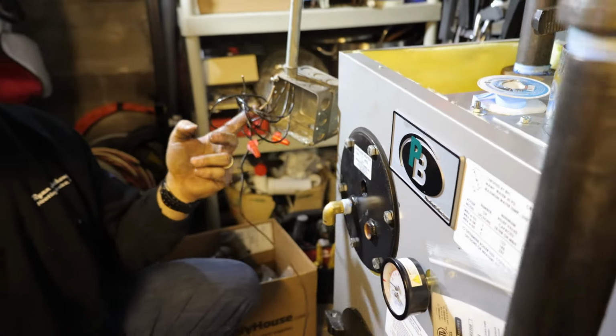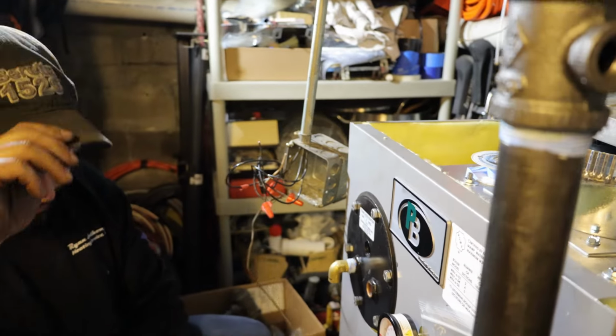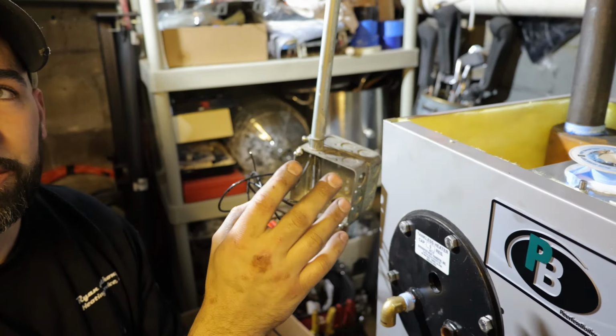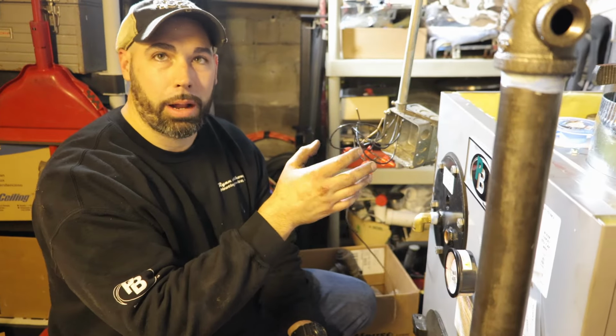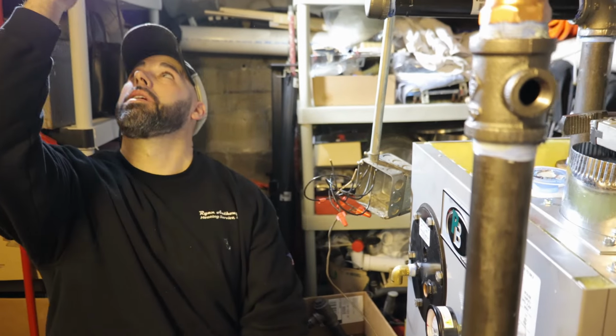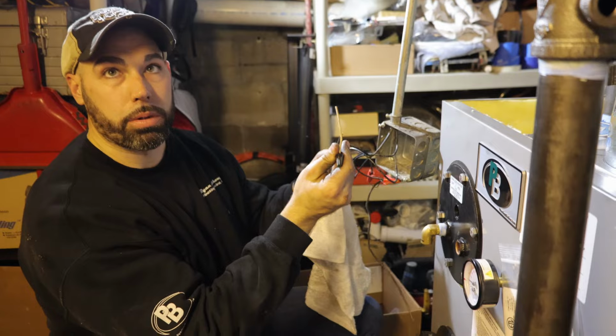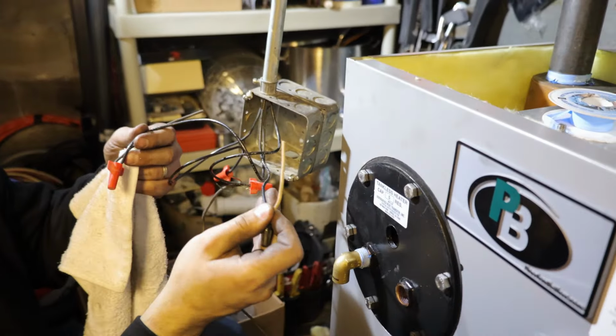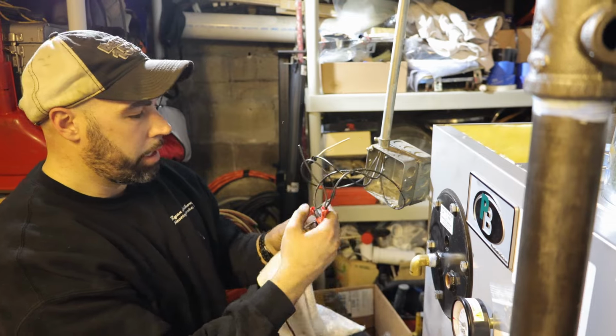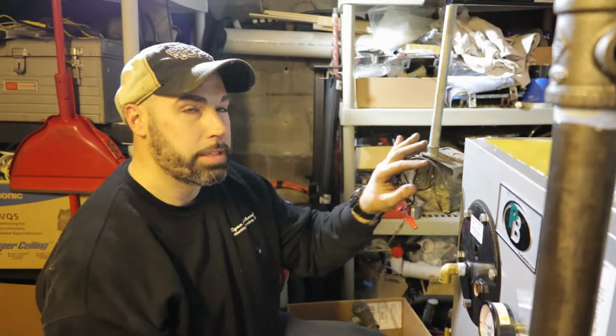Okay. So, see the wiring? You guys see anything weird here? Four black wires. Never trust the wiring. So, we labeled it different. We have the switch right up there. Either years ago, technicians would try to trick other technicians so you didn't know which was the hot, which was the neutral, which was the thermostat. Or they just didn't have black and white wire coming from the box up there from the switch. So they came down in two blacks. But when I cut the boiler out, I labeled what was my neutral. So I still have my white wire. So when I reconnect it, not only will we test it, we'll also have the wiring that's there. So I know my hot and neutral's there. And then here's my thermostat. I still have it attached. So we know what's what here. All right? Silly technicians.